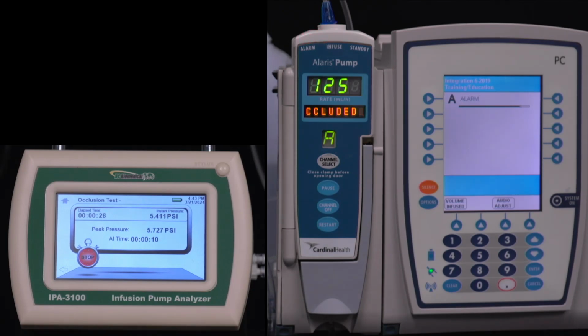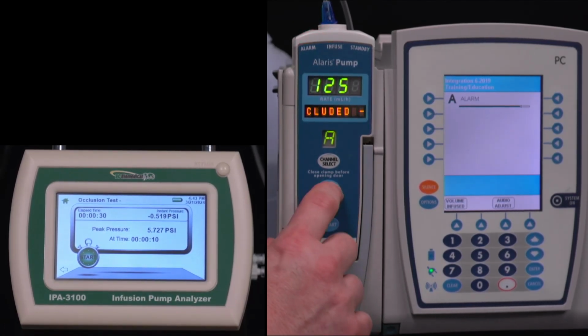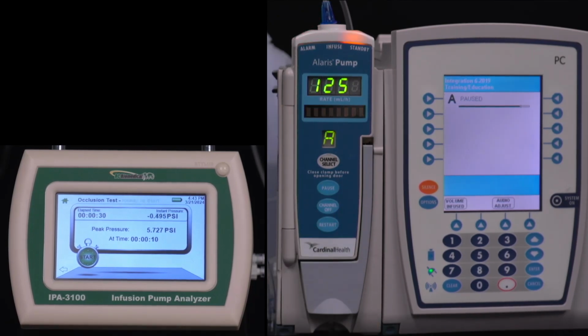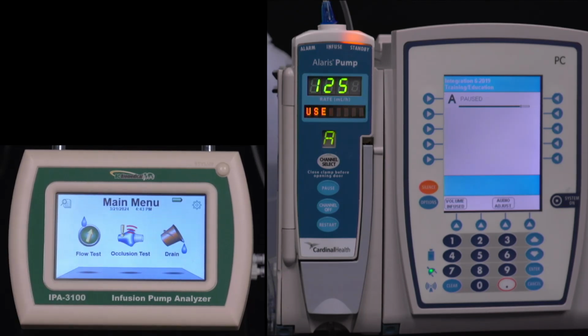Okay, so it detected the alarm. We can go ahead and stop the test, and it will tell us that our occlusion pressure was 5.7 psi, and it occurred at 10 seconds. And again, we can go back and compare that with the service manual and determine whether that's good or bad. Okay, so that's a demonstration of the manual test modes, right?